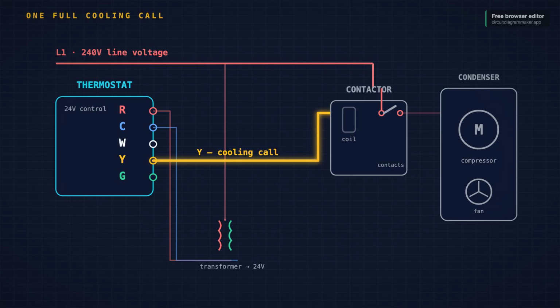And here is the key idea of the entire system. The contactor is just a big relay. A relay is a switch that electricity flips instead of your finger. The 24 volts on Y energizes the contactor's coil. That coil becomes a magnet. The magnet yanks a set of heavy contacts closed. And those contacts connect the full 240 volts to the compressor and the condenser fan.